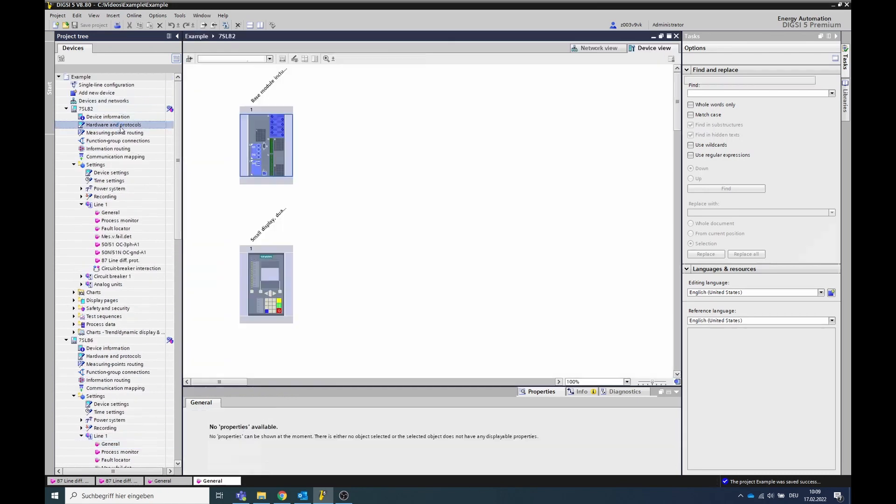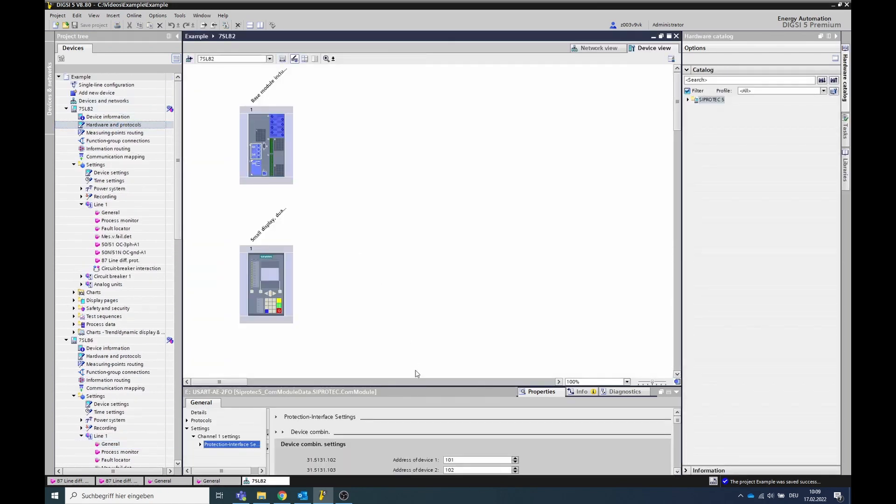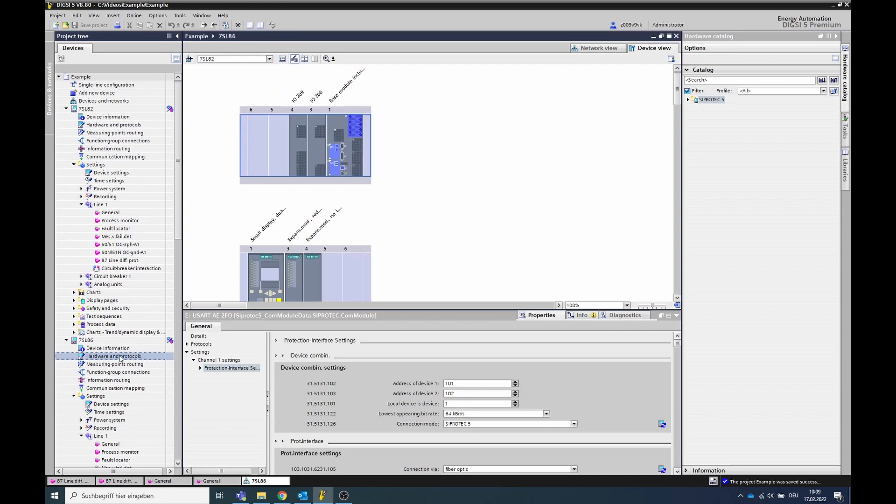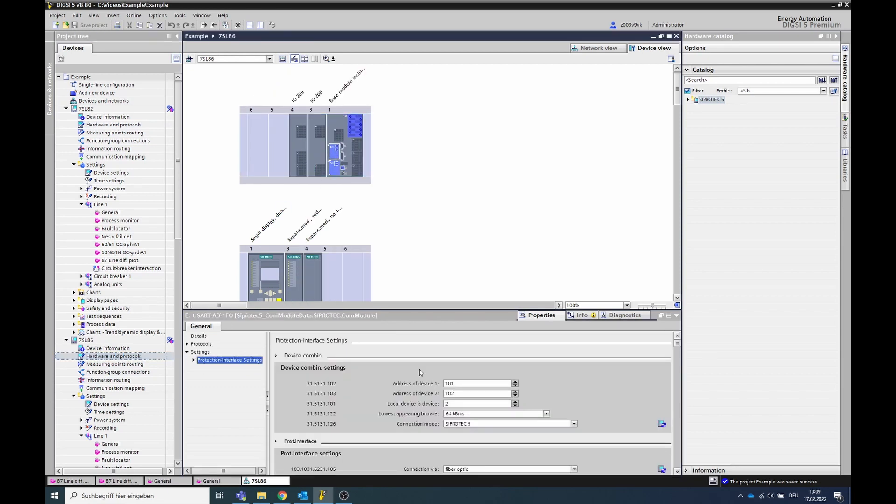In the project navigation, go to hardware and protocols and double-click on the module over which the protection interface communication runs. Check the address is set for both devices. For parameter 101, local device is device X, both devices must have different values set.